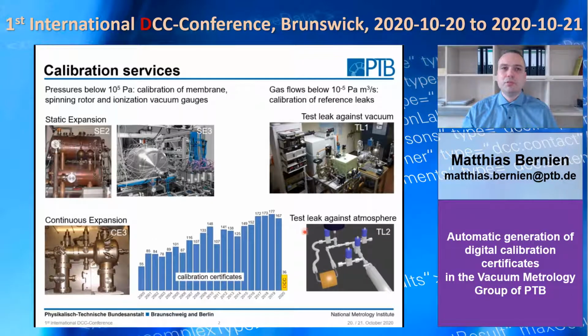The vacuum metrology group is disseminating the scales for pressure below atmosphere and the scale for small gas flows below 10 to the power of -5 pascals cubic meters per second. For this purpose, a number of primary standards are operated. Membrane and spinning rotor gauges are calibrated with a static air expansion system, where a fixed amount of gas is expanded from a small volume into a much bigger one, and if the initial pressure and the ratio between the two volumes is known precisely, a well-known pressure is generated.